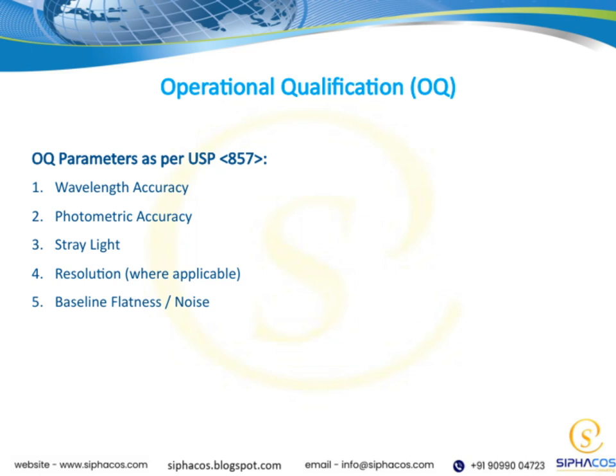Stray light is another critical parameter. It's about checking how much unwanted light reaches the detector, which can interfere with the results. We want to keep this as low as possible to maintain the integrity of our measurements. Then, where applicable, we assess resolution, which tells us how well the instrument can distinguish between two close wavelengths, an important factor for complex analyses.